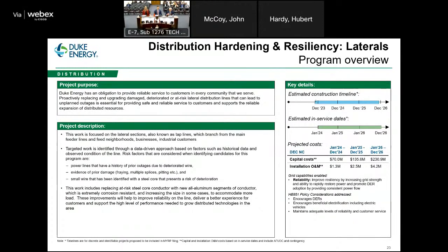The process for this is data-driven. We look at outage history and specific cause codes, as well as the physical condition of the conductor, looking for damage or multiple splices. The most common thing we find is an older vintage high-strength steel core wire that presents a corrosion risk over time, which we upgrade to a high-strength all-aluminum alloy to avoid that corrosion risk in the future.